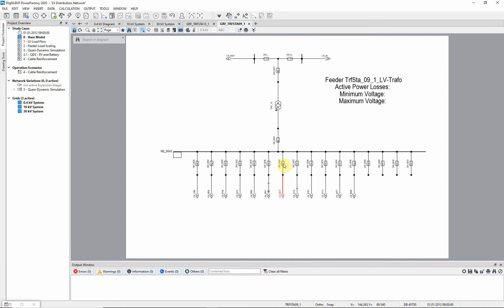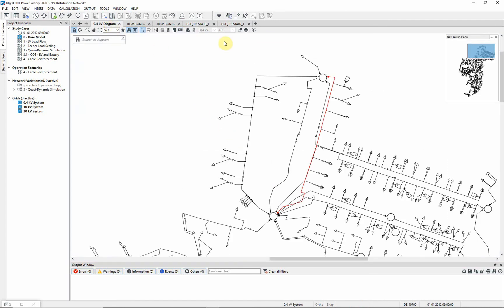You'll notice immediately that the outgoing way turns bright red. Return to the 400 volt diagram, and notice in this diagram also the feeder is marked as red. The diagram coloring has noticed that the feeder is running in a mesh arrangement rather than a radial arrangement.